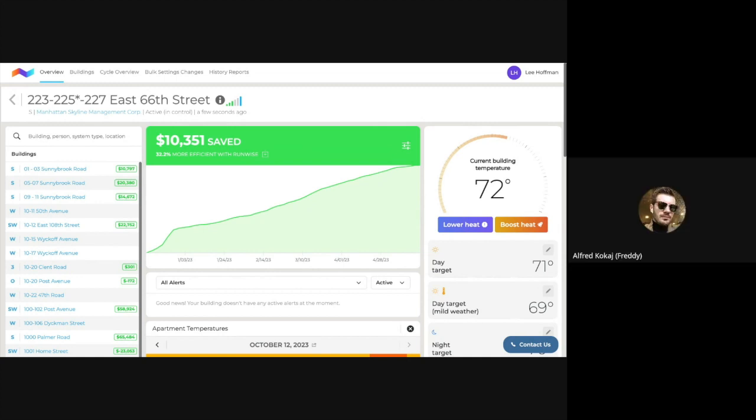Yes. Basically, the things you mentioned are among the things that we have tried. And for some reason that I forgot to mention earlier, there's this specific unit that can't seem to surpass 65, 66 degrees, even when other apartments in that same building reach higher. Even if I increase the boiler temperature more than I should, actually, that unit still remains cold.